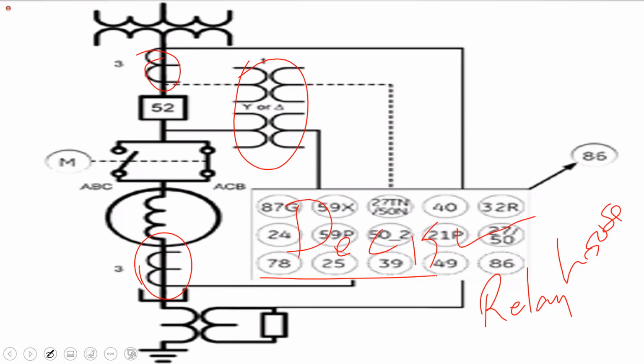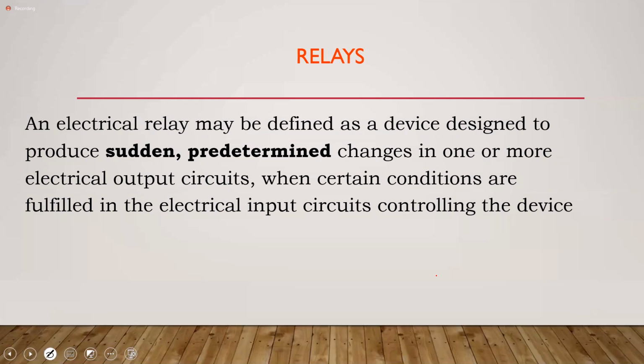So let's start there. Let's start with a simple thing. What are relays? All right? Simply put, and these are the keywords, a relay must produce a sudden, predetermined change in one or more electrical output circuits when certain conditions are fulfilled. So in effect, the relays are the brains of the system, but their brains are only as effective as ours. In other words, they can only do what we have instructed them to. Right? So they are going to produce sudden, predetermined changes, right? And these are what we then refer to as the decisions that the relays make.